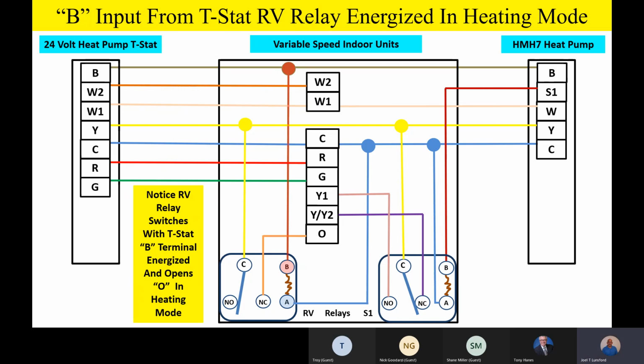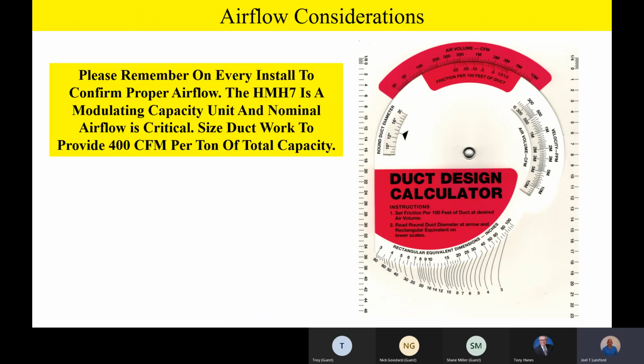Okay, team. Well, some final things as we kind of start wrapping the program up a little bit. I want to please remember to remind everyone to please, on every install, to confirm proper airflow. The HMH7 is a modulating capacity unit, and nominal airflow is going to be critical. So please size your ductwork to provide 400 CFM per ton of total cooling capacity. So if I've got a 2-ton unit setting outside, I need 800 CFM of ductwork capability. If I've got a 3-ton unit setting outside, I need 1,200 CFM and so on. So 400 CFM per ton of total cooling capacity.